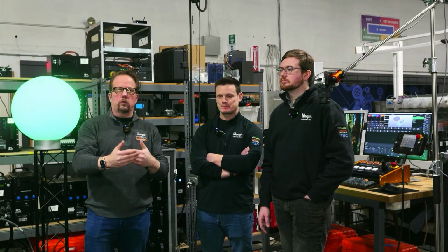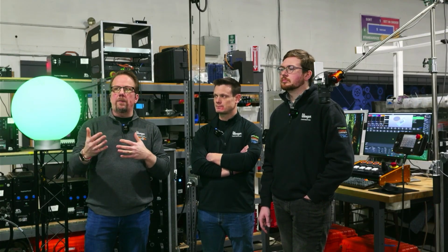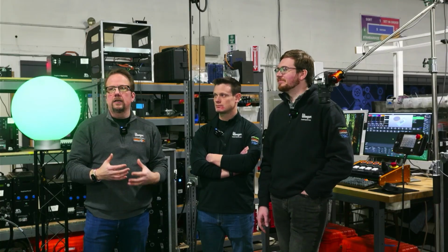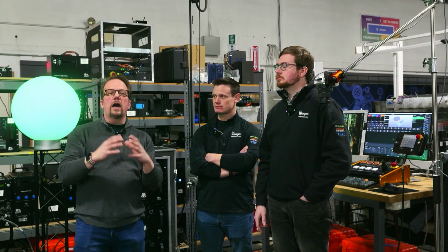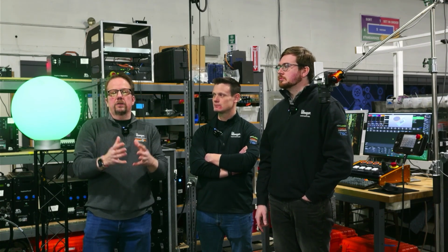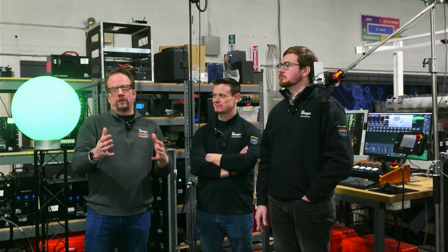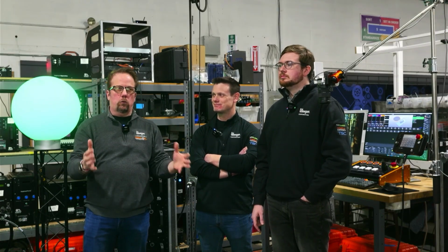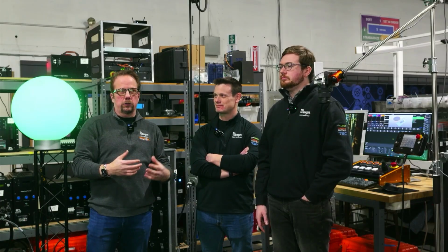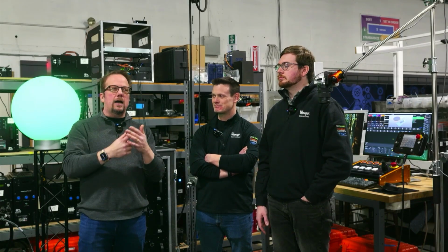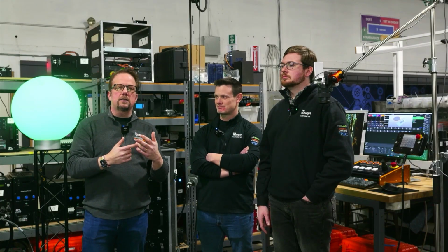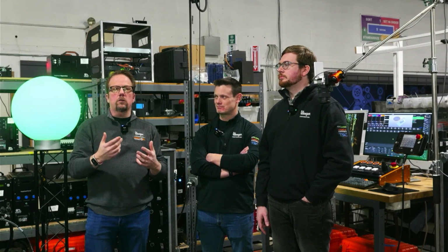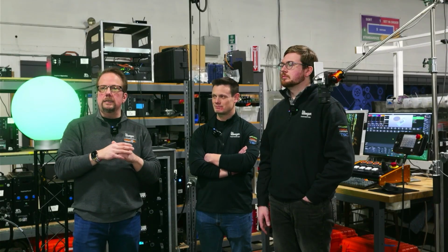When we do a scoreboard hoist, the likelihood that you're going to swap out a 50 horsepower cabinet is pretty low. So we're going to just go ahead and hardwire it and save on the connectors and all that stuff. And it will not be the normal modular thing. But the gig there is that we don't have another 50 horse bespoke custom cabinet for the scoreboard sitting on the shelf here that we could swap out for you. But if it's a stock size of Stagehand, whether it's Stagehand Pro, Stagehand Line Set, Stagehand Apprentice, those are going to be connectorized so that we can exchange them with ease.